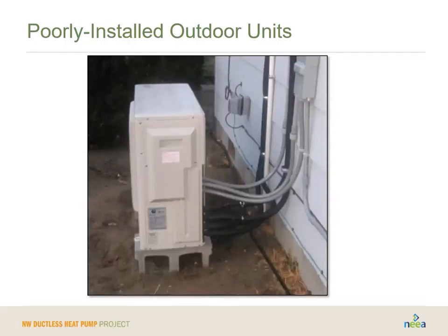So here, clearly they did not put a pad on compacted ground. You can actually see they put this on these concrete blocks and it's sinking into the earth. This is not a long-term good solution. It is also not earthquake strapped, and that insulation does not appear to be covered either. So this is really failing on several different levels. It may work for a while, but over time, this device is going to be a challenge to live up to its 10 to 20 year life.